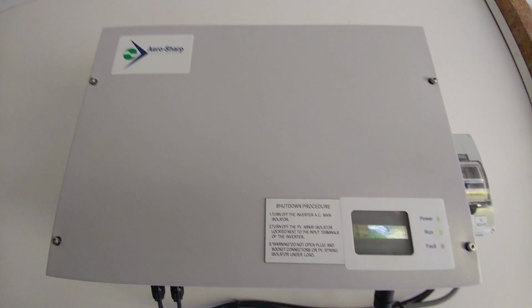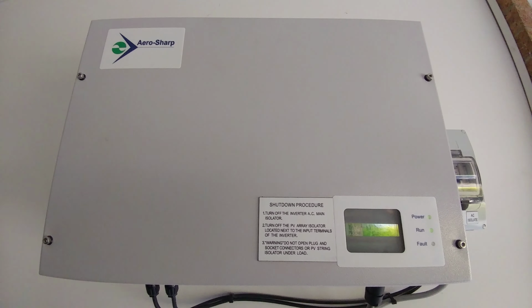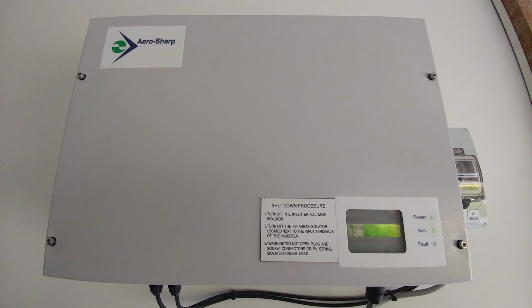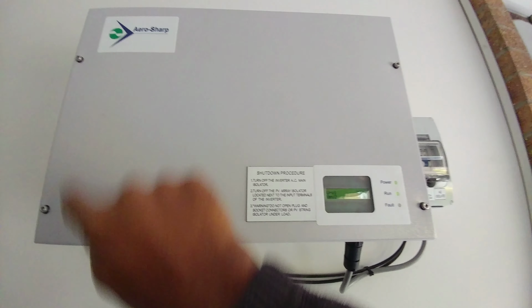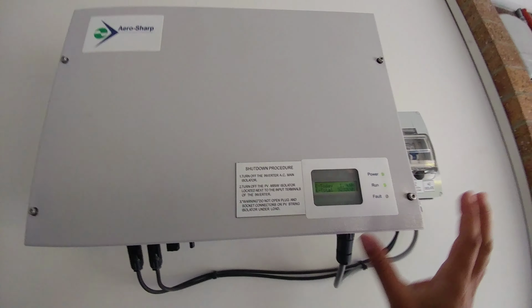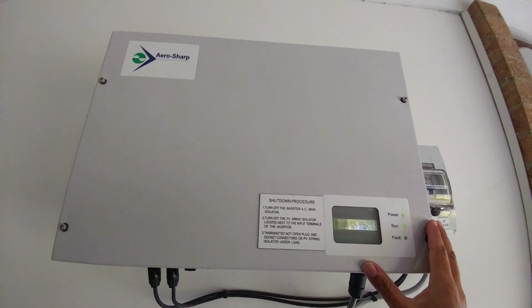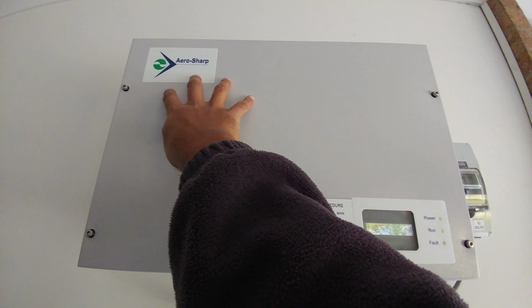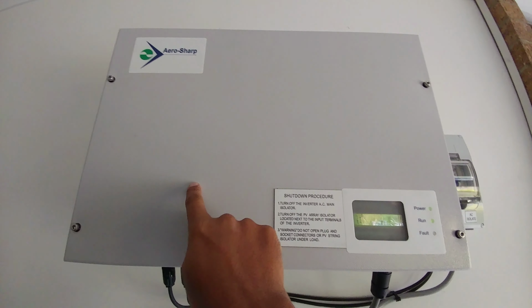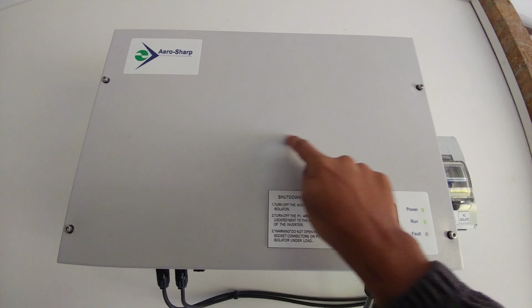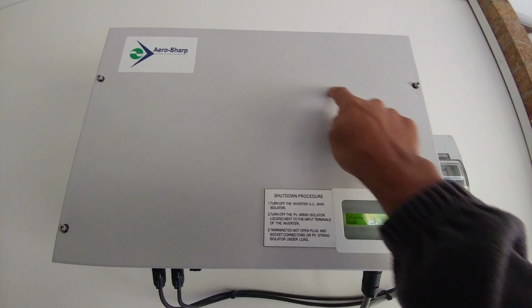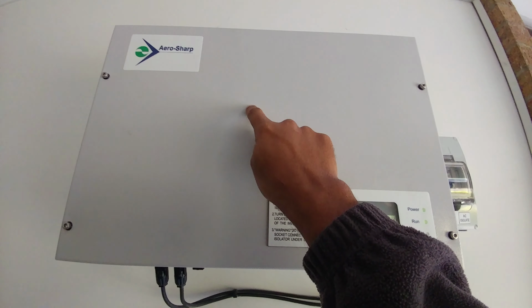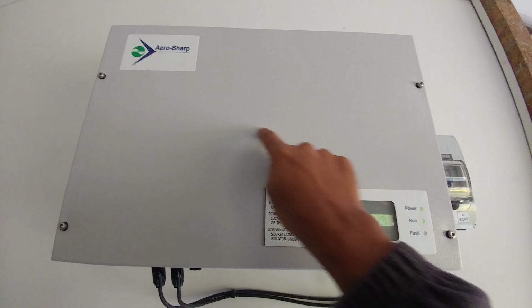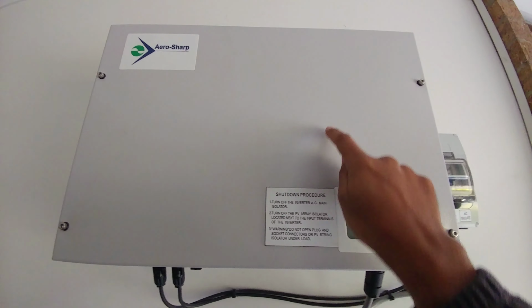So I should say that from what I can gather from this unit, the inverter got repaired, and inside this unit, what you actually have is, if you were to remove these four bolts after these connectors have been disconnected, the unit has been left to sit for at least an hour. Inside, you will have the transformer here, a whole bank of electrolytic capacitors, and above in here there will be a control board just here, and below that control board is another board, which is a switch mode power supply. And that has electrolytic capacitors.